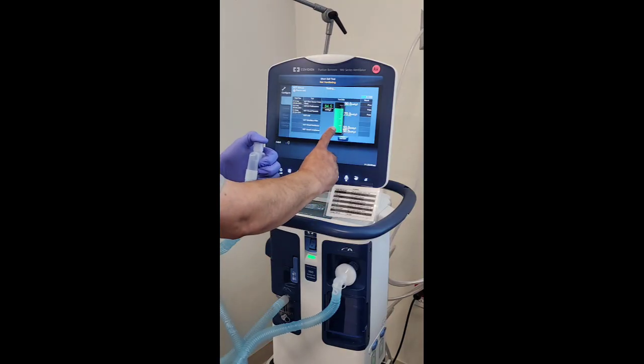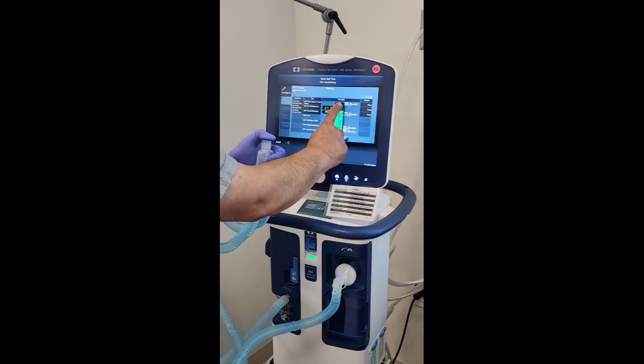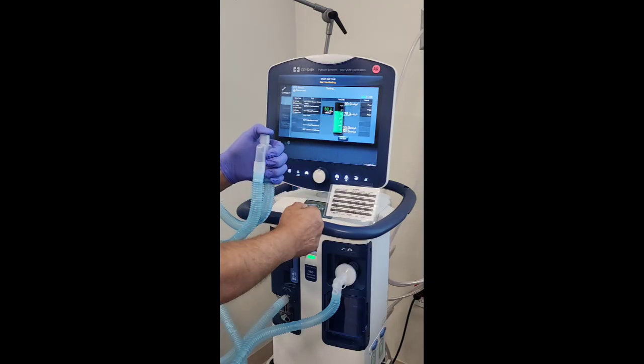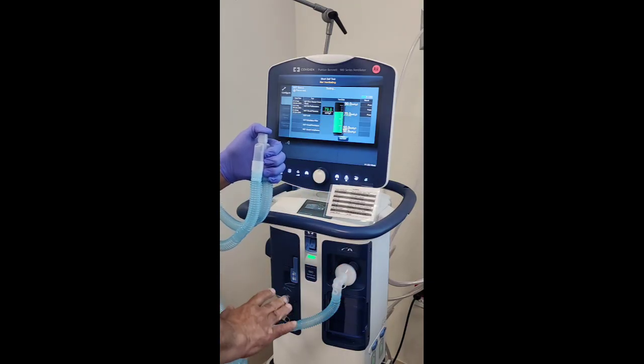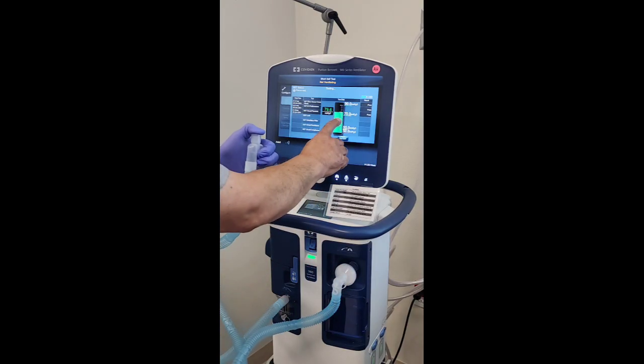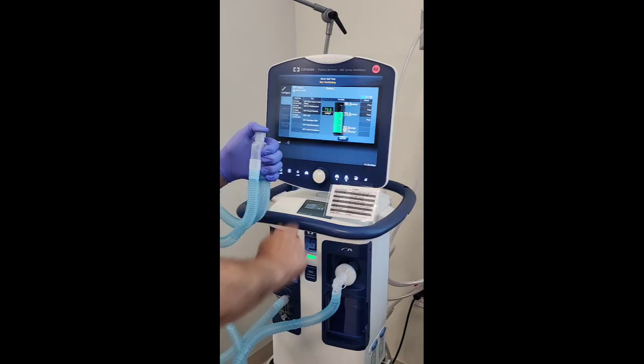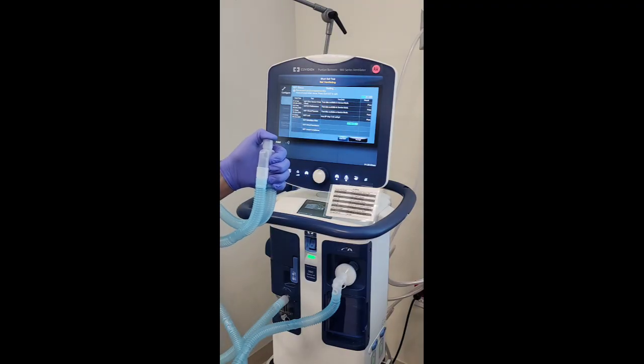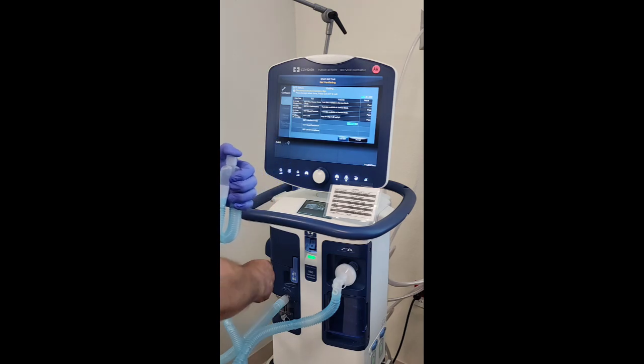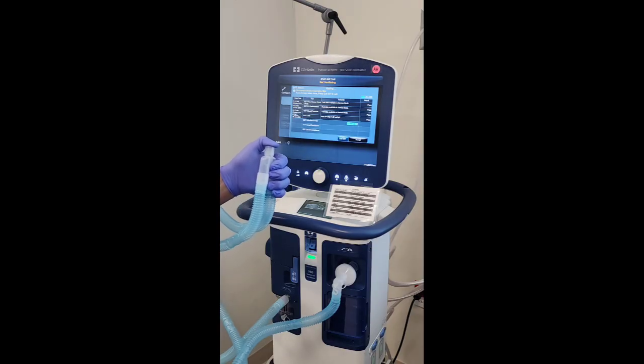So you can see it's going all the way up to 90, and it's holding that as long as I have my thumb on here, preventing any kind of leaks. And it needs to stay above 75, which it looks like it passed. It's 79.6. And now it's checking the exhalation filter. That filter I showed you guys before down here. Make sure that's working properly and there's no issues with that. I'm still holding pressure here.